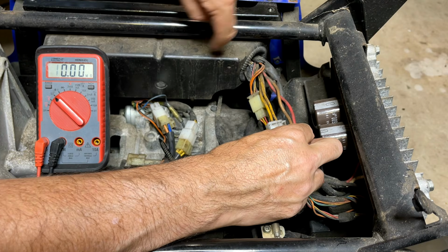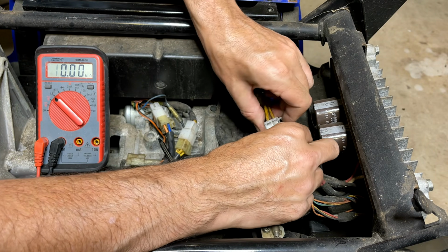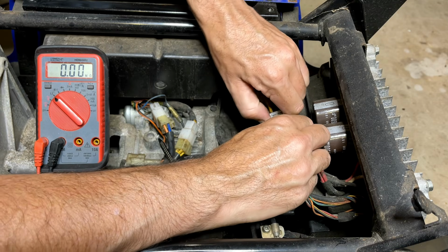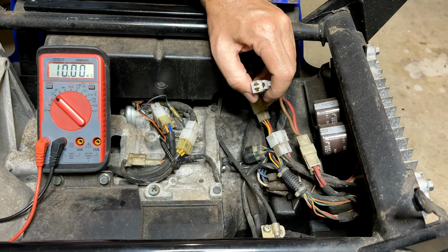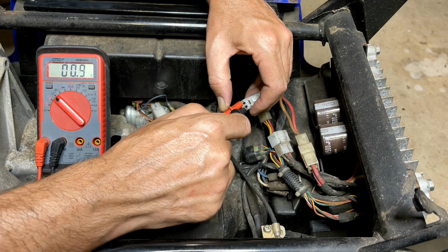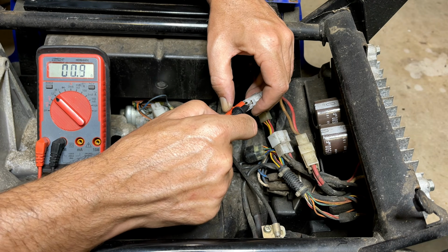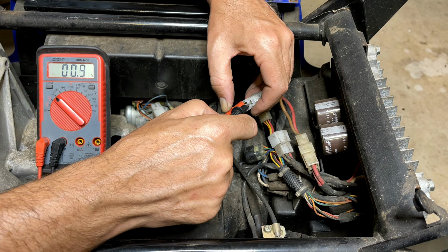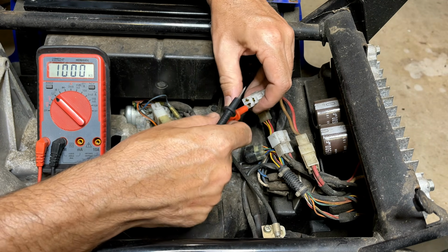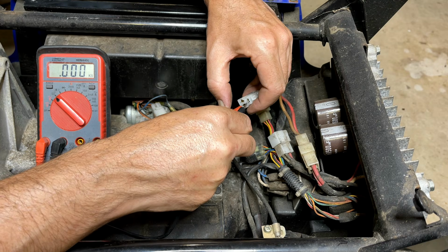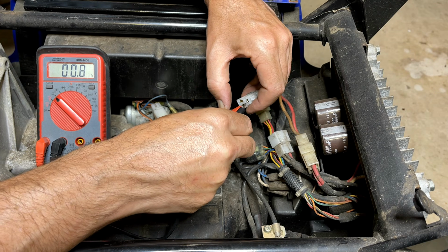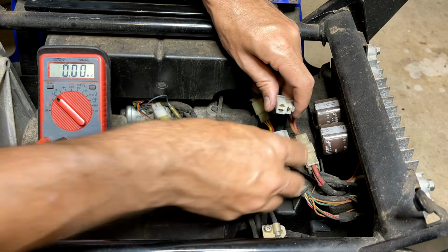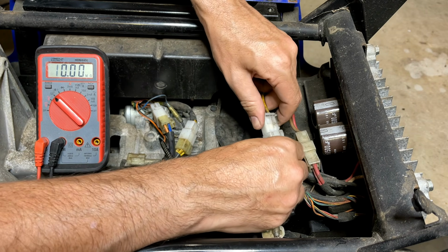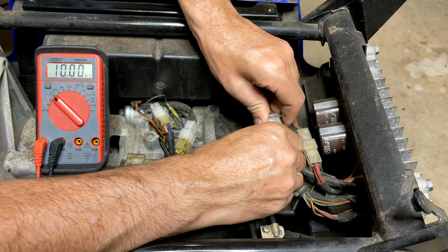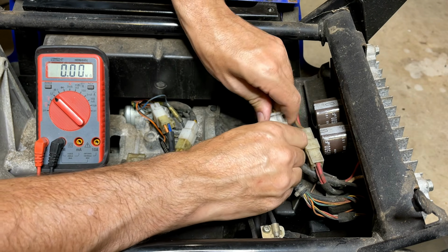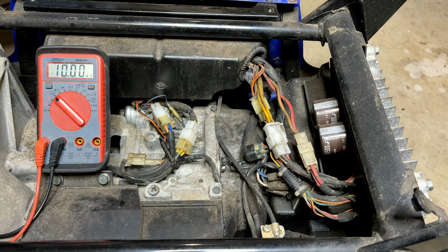So the yellow wires go through this box and then out, so I'm going to check the connector over here as well, to make sure we get that same reading of about 0.8 ohms. Yep, that looks good. That's good. And same there, so I'd say the input to the inverter is good. Now, I don't know what the ohms readings should be on this, I'm going to try to look it up. But the fact that all 3 legs are consistent is a very good sign.